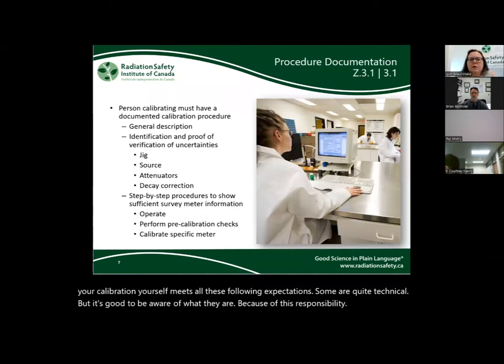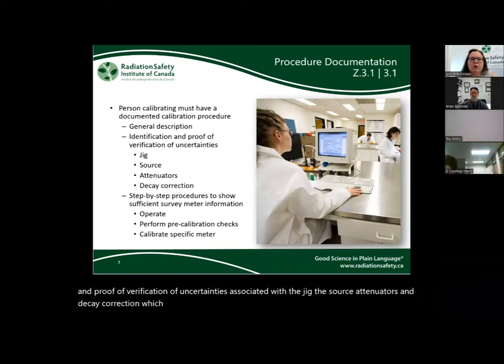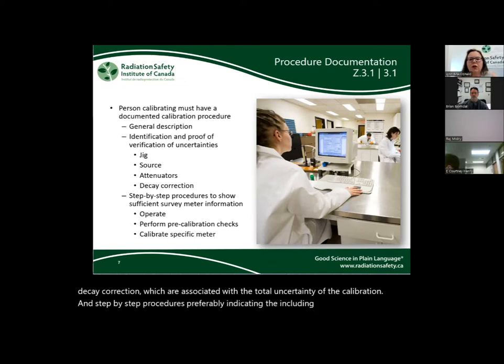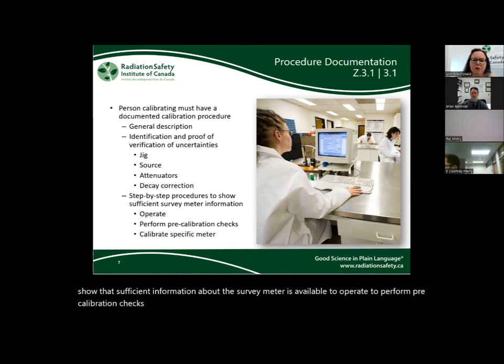Before calibrating any specific make and model of survey meter, the person conducting the calibration shall have available for inspection and assessment a documented calibration procedure consisting of a general description of the method of calibration, an identification and proof of verification of uncertainties associated with the jig, the source, attenuators, and decay correction, which are associated with the total uncertainty of the calibration, and step-by-step procedures, preferably including manufacturer's manuals, to show that sufficient information about the survey meter is available to operate, to perform pre-calibration checks, and to calibrate the specific survey meter.